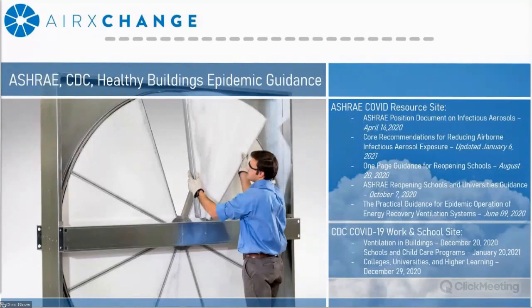So the ASHRAE guidance is largely based on mechanical operation guidance, and that has been translated over to the CDC with a similar tone, or even the same guidance being presented by both sources. However, the CDC includes additional guidance as it pertains to source control, sanitizing, traffic flow patterns, and more in that regard. But the focus of this conversation is going to be the mechanical operation.